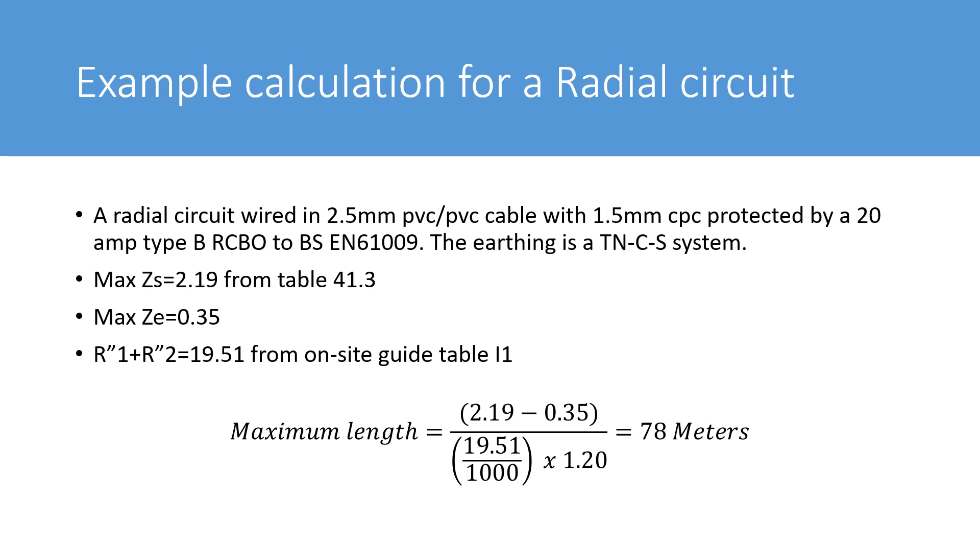So here we have the equation at the bottom. The maximum length is equal to, in brackets, 2.19 minus 0.35. And that's divided by 19.51 divided by 1000, and then multiplied by the correction factor of 1.2. And that gives us the answer of 78 meters.